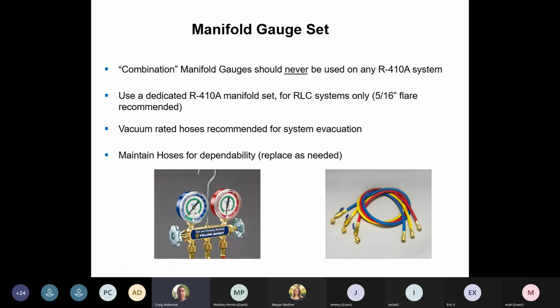So manifold gauges, combination manifold gauges should never be interchanged between different freons. Different freons have different oils. Different oils break down other oils. So if you're working with R22, you're working with 410, 404A, have a set of gauges ready for each unit.